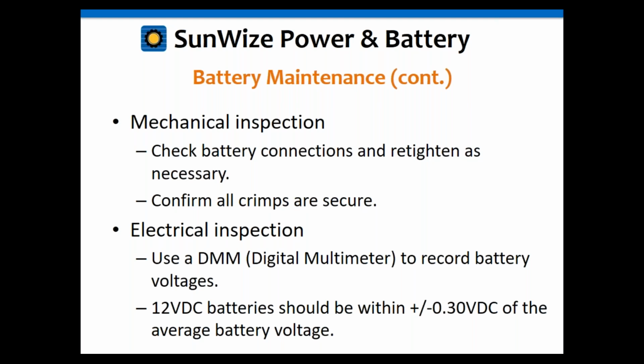We'll use a multimeter to record the battery voltages. Going back to that slide I showed before, which showed that the voltages were off, that's not good. One of those is off by as much as 0.4 volts, and that shows you there's a problem. You should be within 0.3 volts in a 12 volt battery. Actually, I'd like to see them be even less than that, to be honest. I'd like to see within 0.1 or 0.2. If you're off by more than that, there's probably something going on. Your batteries are getting unbalanced, and you should investigate. Because if it stays that way for long, then you probably have a bigger problem with your batteries, and they're probably going to fail prematurely.